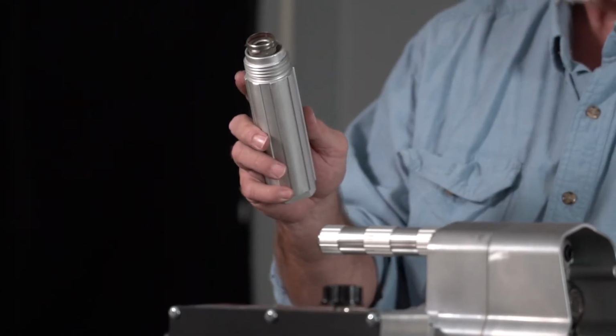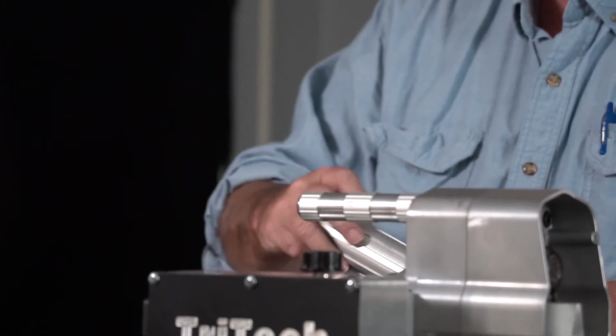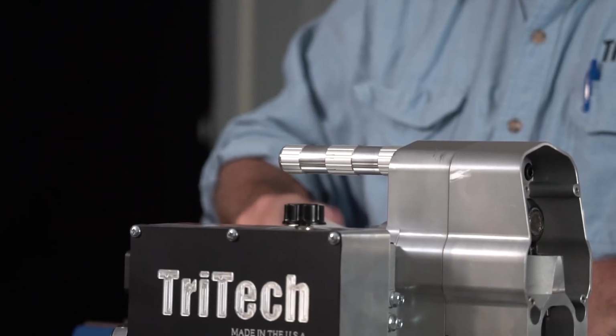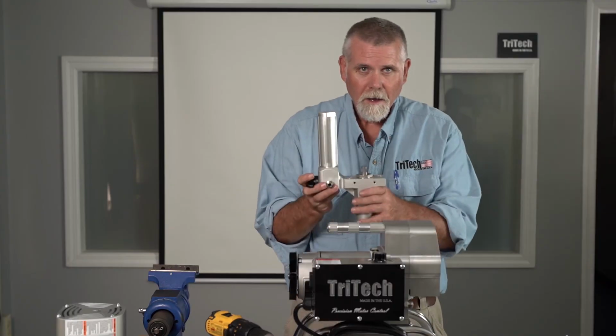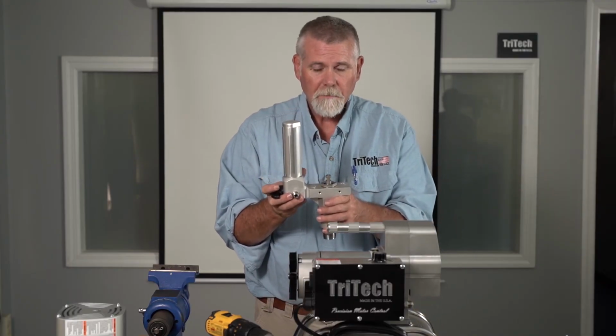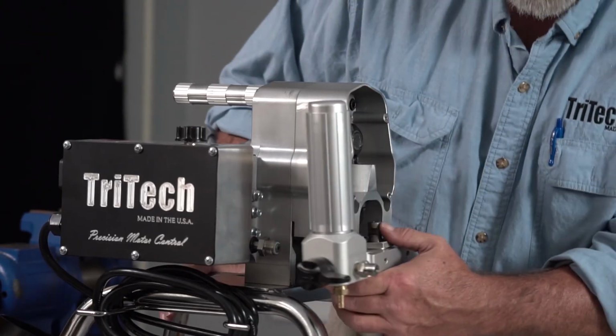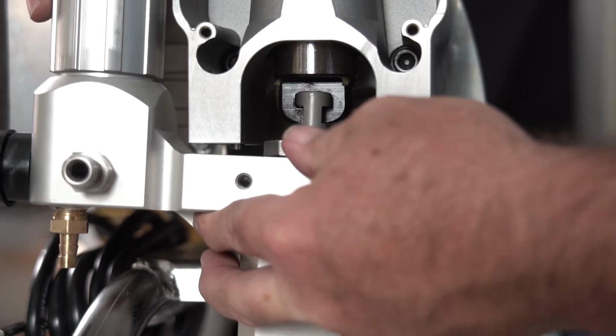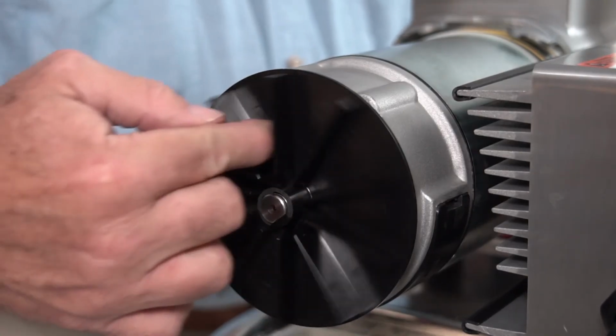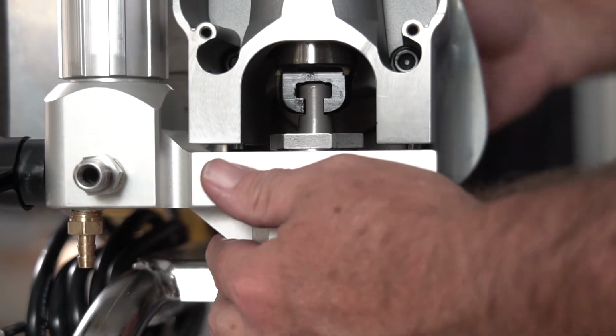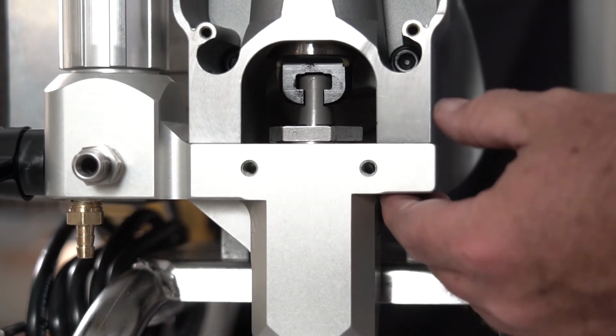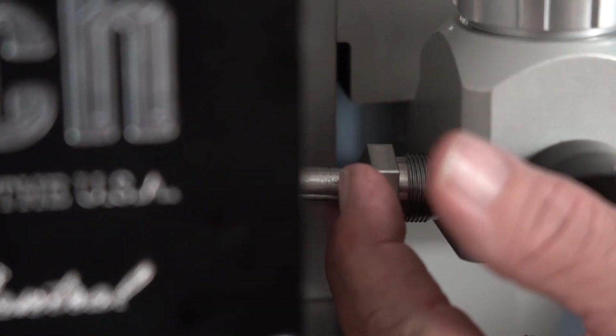And now your filter and your filter support and housing are clean. You can reinstall them. Now your pump is ready to go back onto the unit. Take your fluid manifold, slide your piston onto the crank slider assembly, and then rotate the fan to bring the fluid section up to line up on the dowel pins. Once that's in, then you can slide your transducer assembly forward and get the transducer retainer started. You don't want to thread this all the way down just yet.